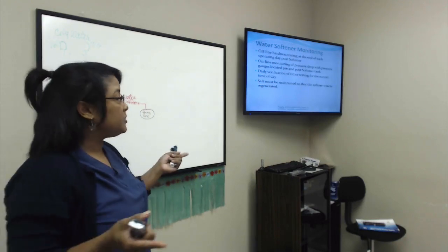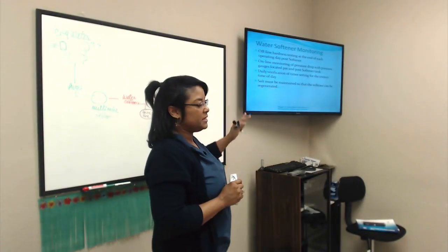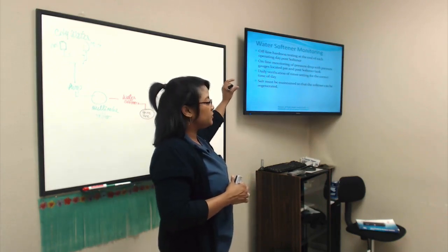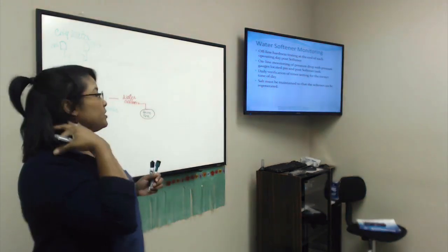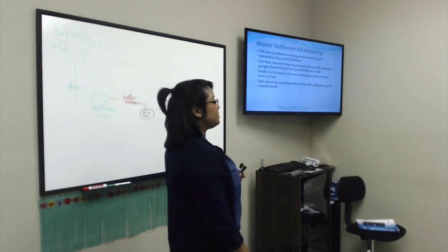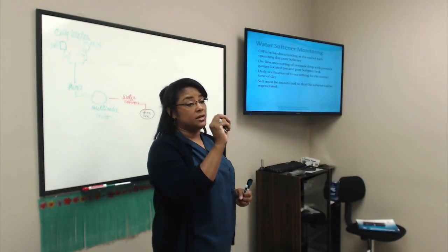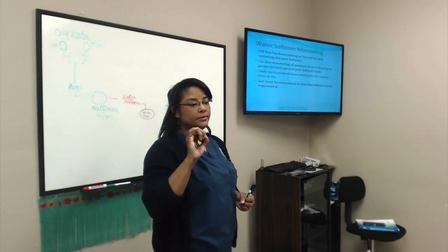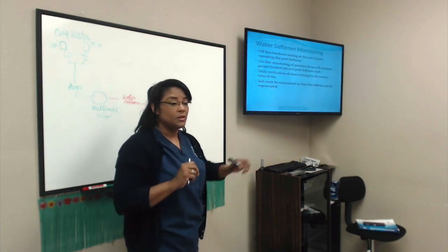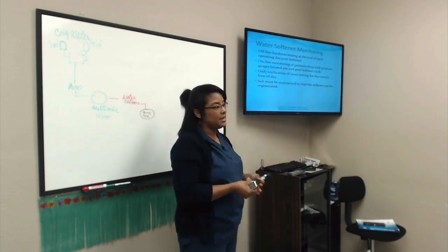So online monitoring of the pressure drop with pressure gauges located pre and post softener tank. What this means is, how do we monitor this is working? Because there are pressure gauges that are going to tell us that the pressure dropped. Daily verification of the timer setting for the correct time of the day. The softener has a timer. When you go back there, if you're the person testing the water in all these systems, there's going to be a log that is going to ask you about the time on the softener. Okay, that time has to match the actual time.